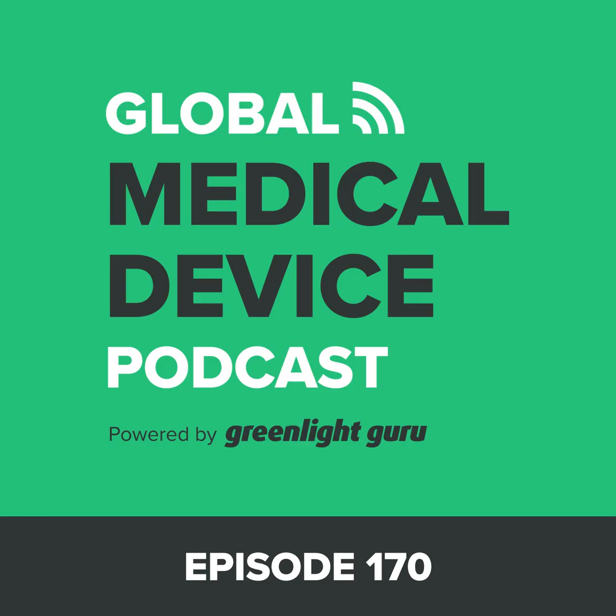Yeah, and software is one of those tricky things too, in that there are a few different practices, so to speak, and risk-based approaches like determining level of concern. And if you're outside the U.S. and pursuing EU, under the EU MDR they bring in these different risk classes for software. So what about level of concern and risk? How important are these things at the pre-submission stage? Very important. I think these are probably the most important things to have really firmly established before you start the conversation with FDA.